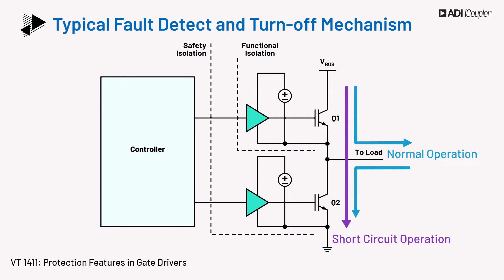In this state, current may reach a damaging level. Short circuits can occur due to detachment of wires. IGBTs and SiC MOSFETs have a limited capability to withstand current based on their thermal capacity. Excessive currents cause a large amount of heat dissipation in the die, leading to failure. Thus, a protection circuit needs to be designed based on current level and the withstand time period of the device, to ensure that the power device is turned off before damage.